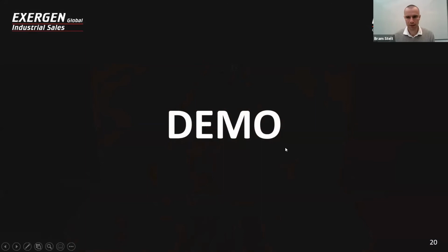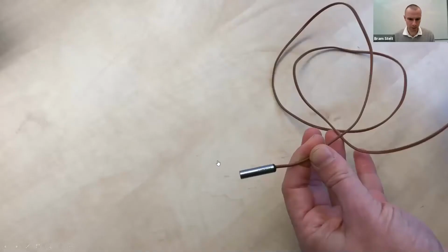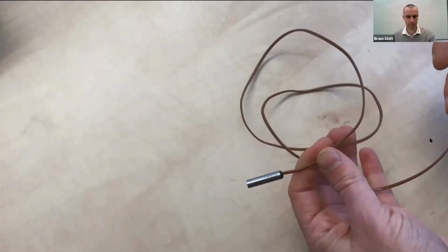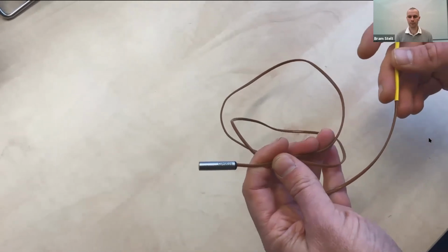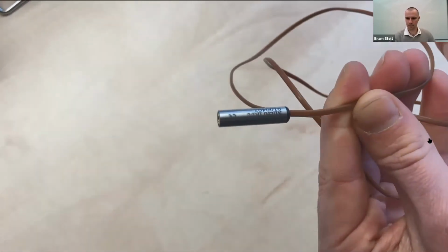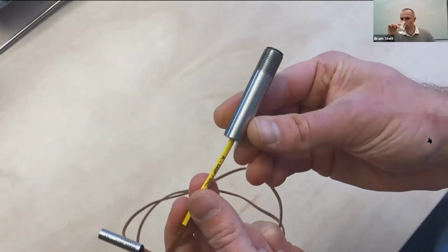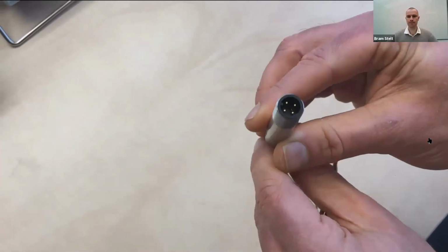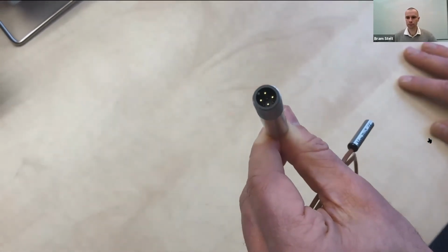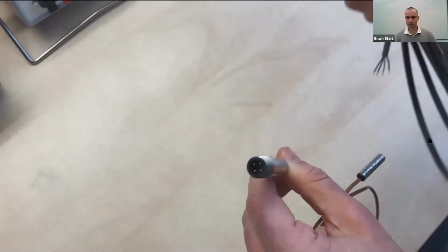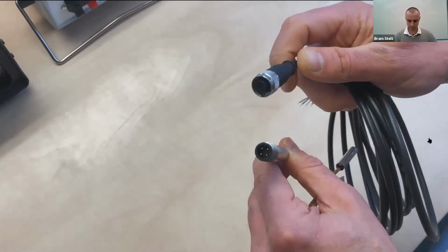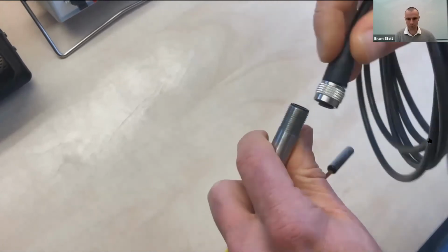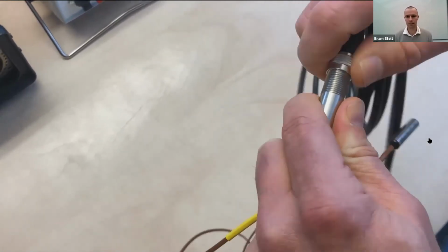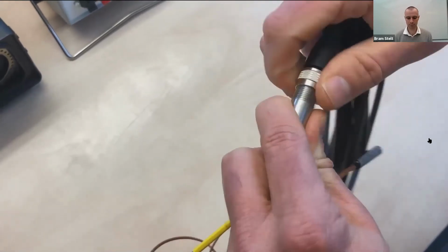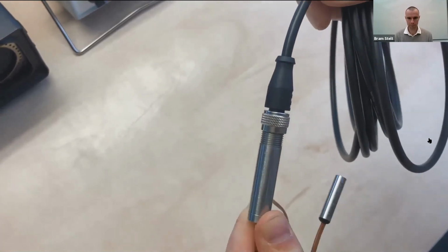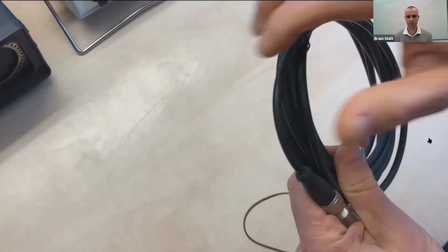Now I'd like to give you a demonstration of how the AutoSmart sensor line works. As explained, you can connect several IRTC sensors to the AutoSmart transmitter. What you see here is the micro IRTC, which is connected to the AutoSmart transmitter. In the back of the AutoSmart transmitter is an M12 connector. And with any AutoSmart sensor that you order, you will get a cable, of course, with a fitting M12 that you can very easily connect to the AutoSmart. Like this, very solid, very reliable. In principle, you can order any cable length that you desire.